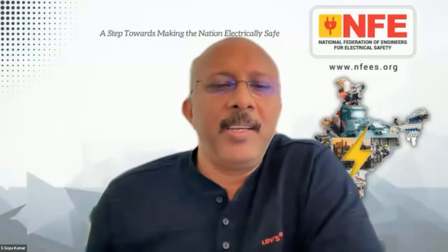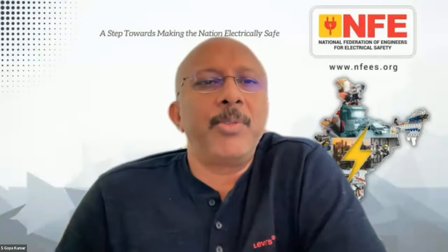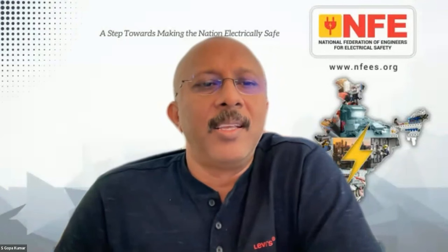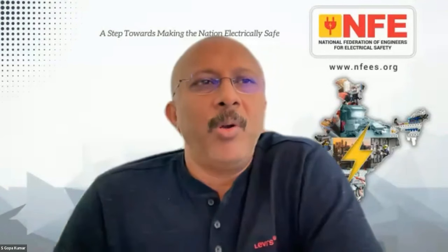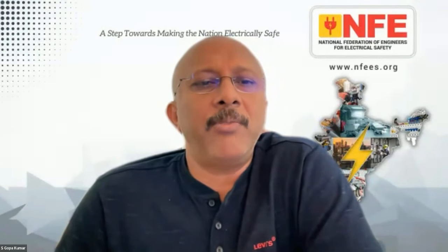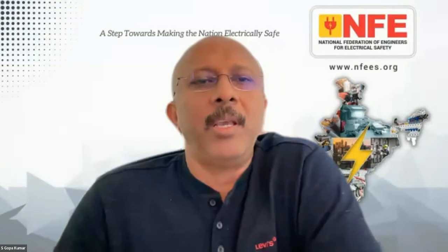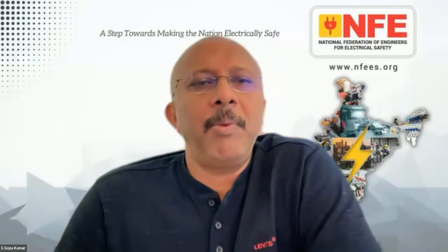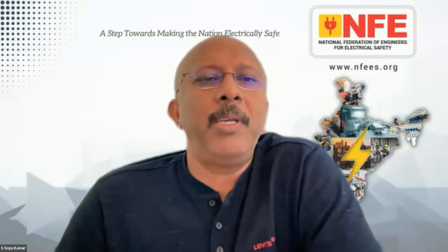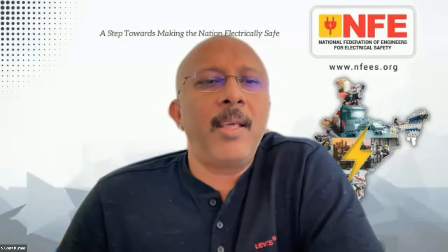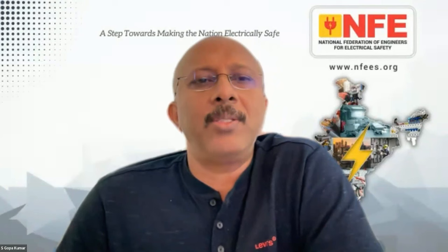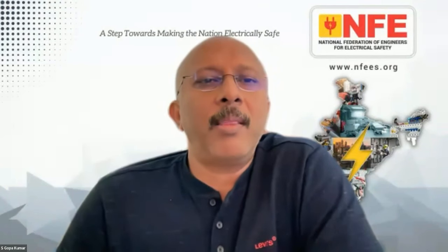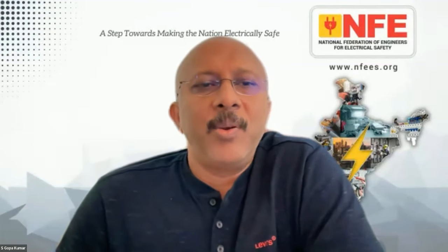Actually, in India, this is a big issue because most of the time we have the habit of using non-standard products. As a result, the leakage currents are much more. Also, I have come across this situation, especially with variable frequency drives and places where semiconductors are used. The leakage currents are much more, sometimes 200, 300 milliamps and sometimes even in amperes. And we also have a funny device sold in the market called a digital grounding device. It's a black box, and it makes a short circuit between neutral and earth inside the installation or closer to a machine. Over to you, Mr. Paul.